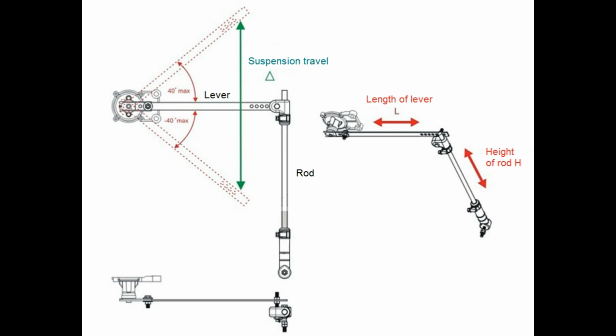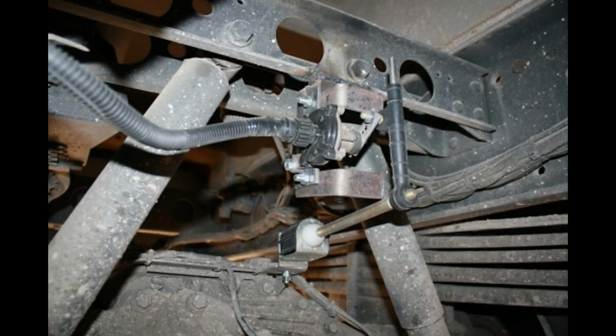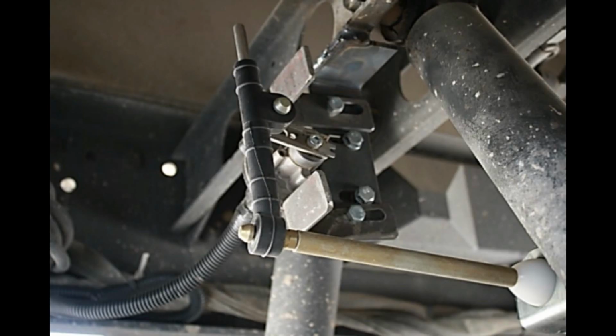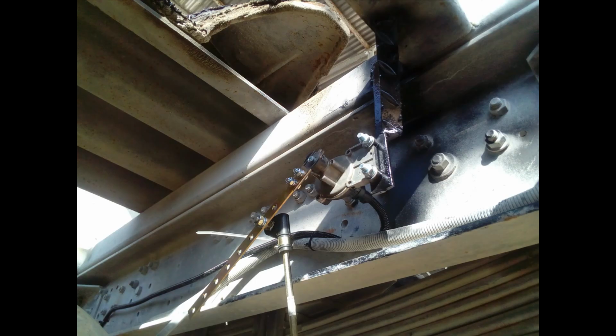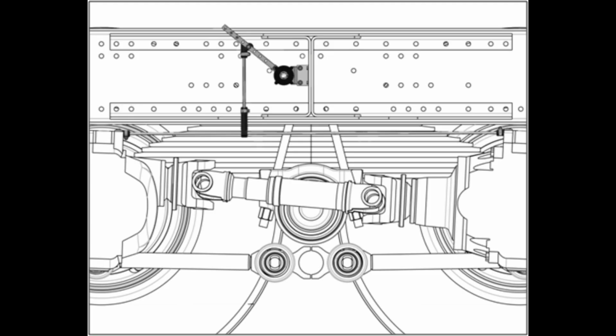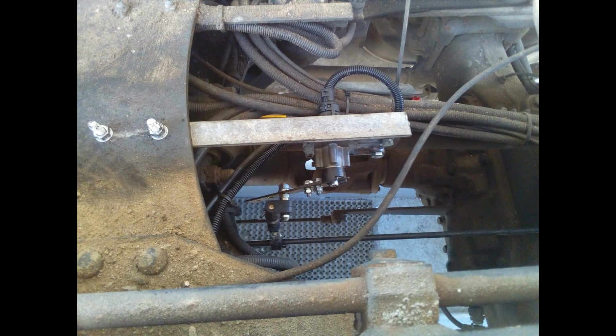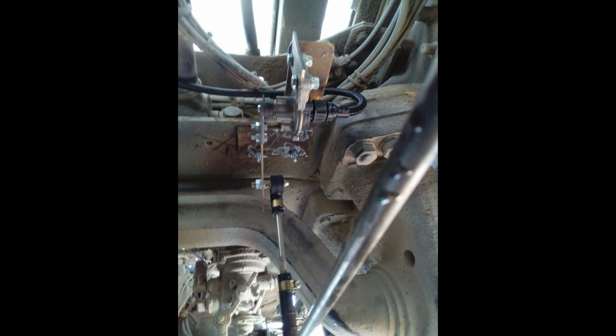In case the spring works on the two axles at the same time, an additional rod should be used. In the middle, it will be connected with a vertical measuring rod. So, we measure the average vertical displacement of the two axles. After the sensor is installed, it is connected via the cable with the system's controller Eurosens Difference T. When all the sensors are connected, we should connect all system elements in one. The free connector of the Difference T unit must be closed with a cable plug.